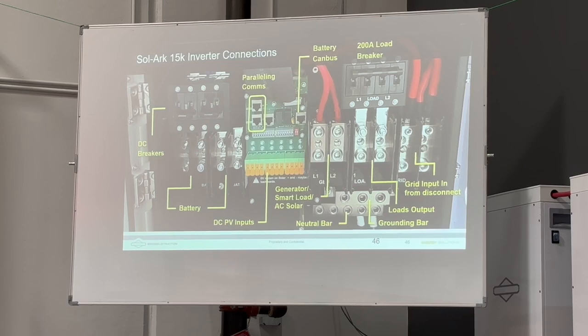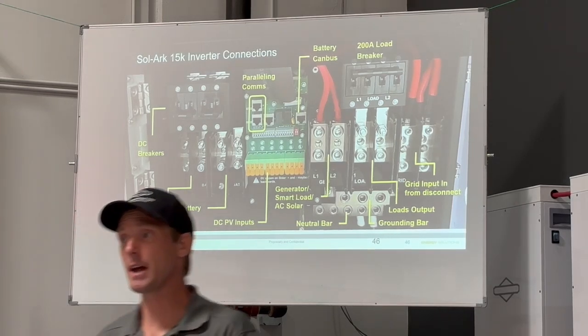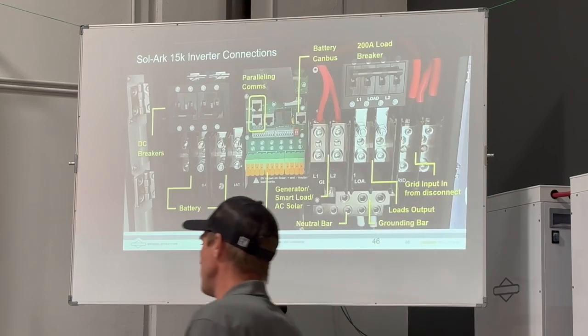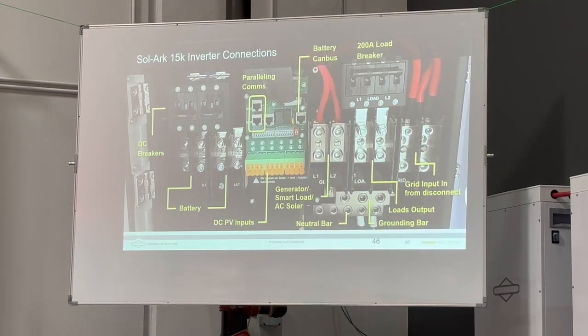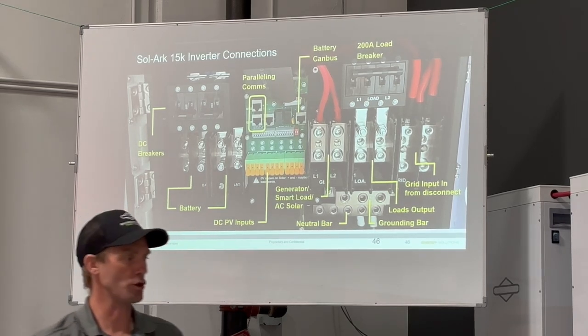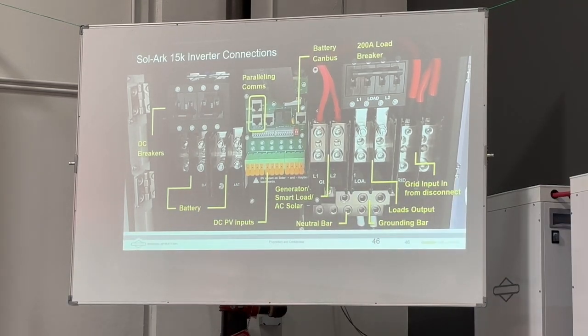So you still want to have a panel. Your panel should have a 200 amp breaker built into it, right? You have to have an in-feed breaker in your panel. And I point that out because you can get panels without it. In fact, I bought this panel without it just because of the size. So then I'm backfeeding a 200 amp breaker to the bus bars here. But you do want to make sure that your load panel, your load center, has a breaker. Okay, let's see. And that'll come back on in another 60 seconds or something. It has to qualify.